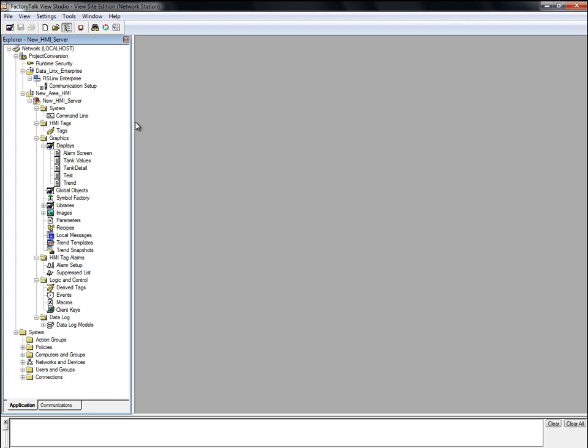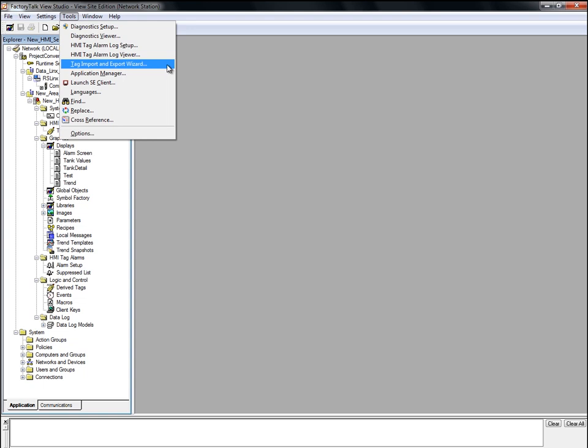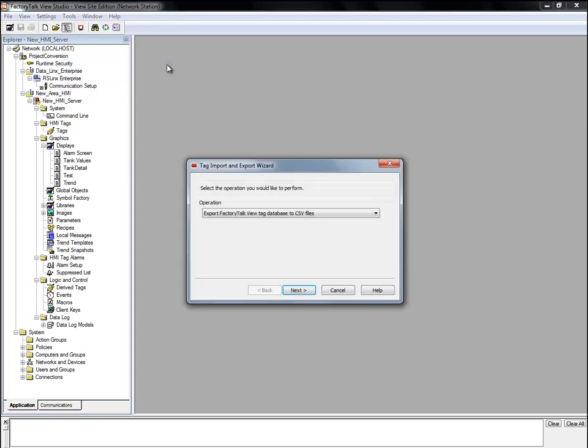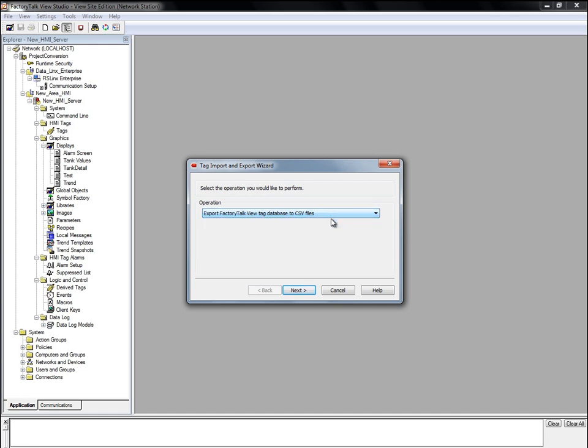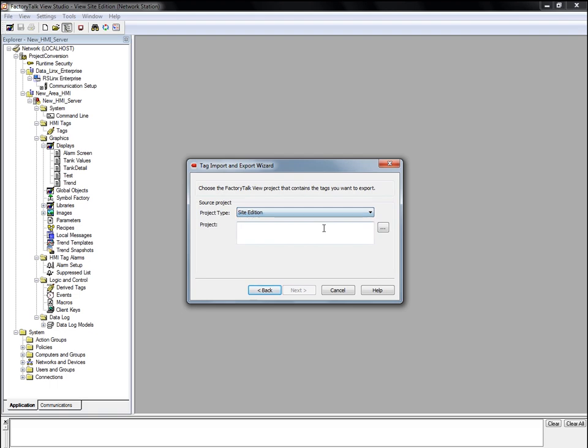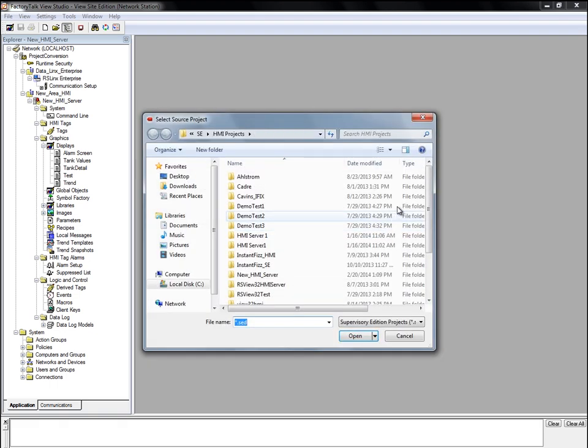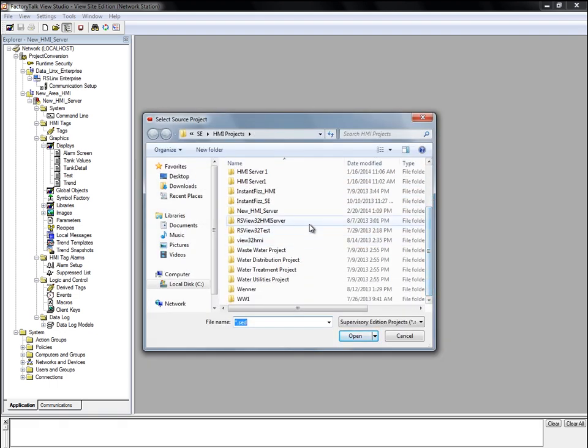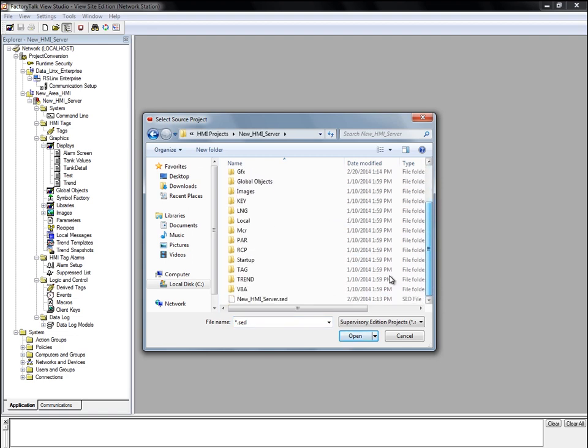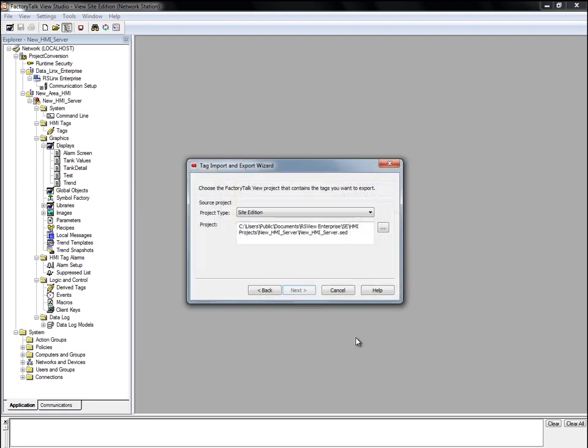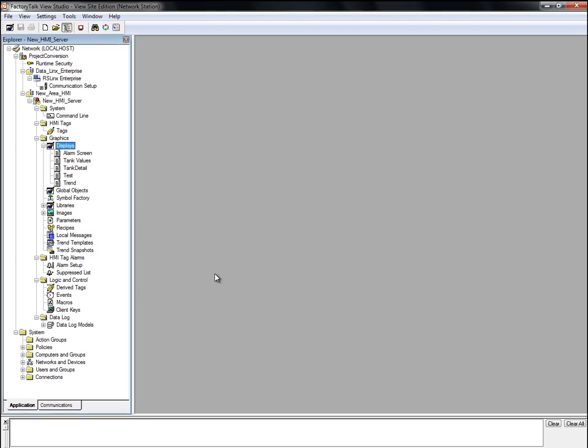The first thing we will do is export the tag database. To do that, we open the Tag Import and Export Wizard in View Studio. We'll choose the Export to CSV File option. Next, we choose the SE project type and browse to the Projects.sed file. Click Finish to export the Tag and Alarm database.